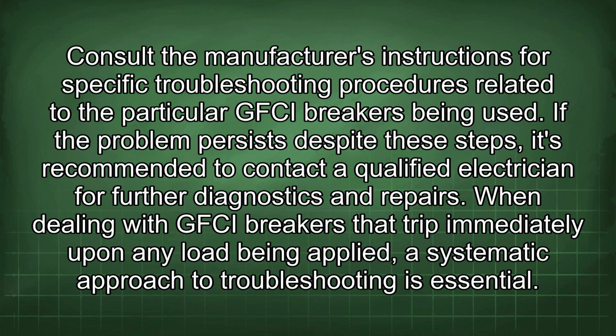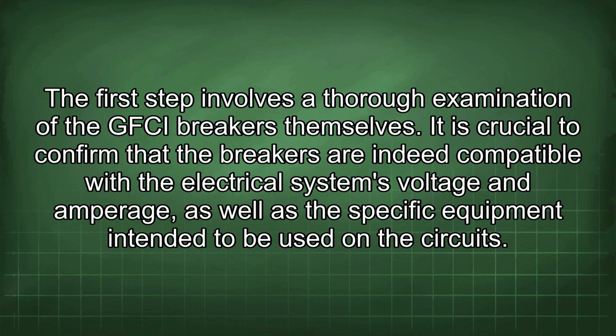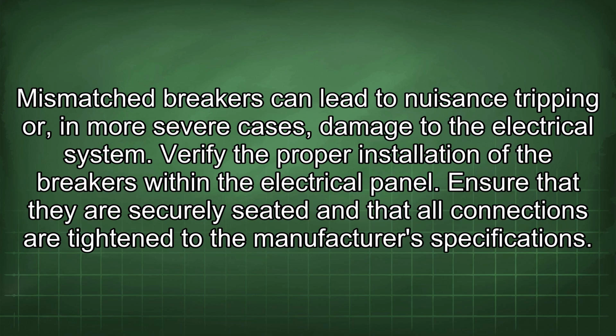When dealing with GFCI breakers that trip immediately upon any load being applied, a systematic approach to troubleshooting is essential. The first step involves a thorough examination of the GFCI breakers themselves. It is crucial to confirm that the breakers are indeed compatible with the electrical system's voltage and amperage, as well as the specific equipment intended to be used in the circuits. Mismatched breakers can lead to nuisance tripping or, in more severe cases, damage to the electrical system.